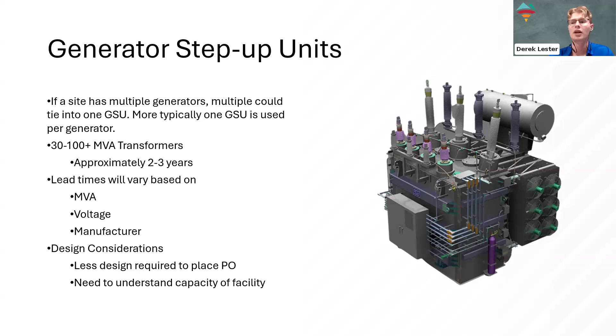Similar to the HV breaker, the good news on design considerations for buying a GSU is you're able to have less design definition in order to get to a PO. That's because you only need to understand the power throughput and the MVA. If you're working with an engineering and procurement partner used to buying this equipment, they should get a spec out relatively quickly. And like with an HV breaker, you can also spend more money for a little more conservatism if you haven't fully defined your design at that point.